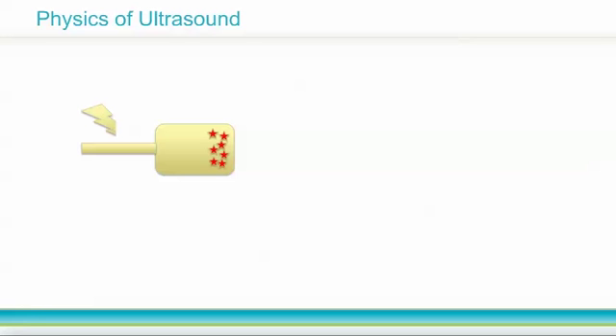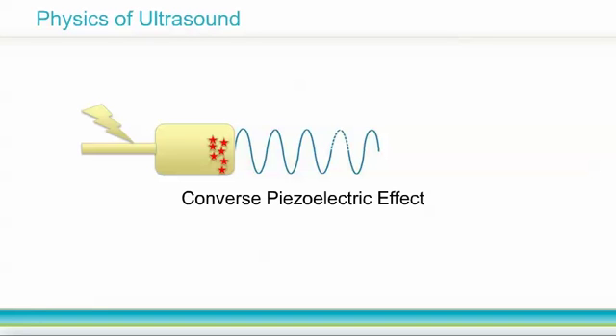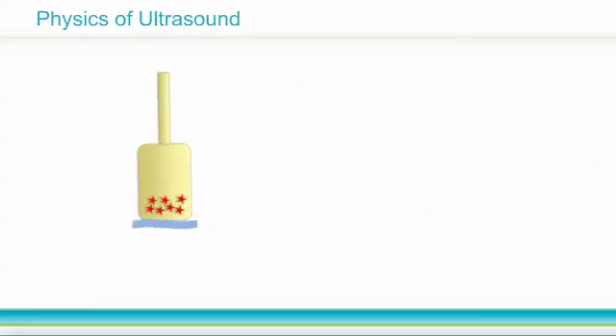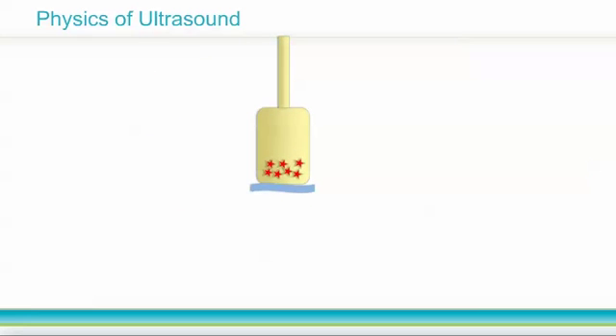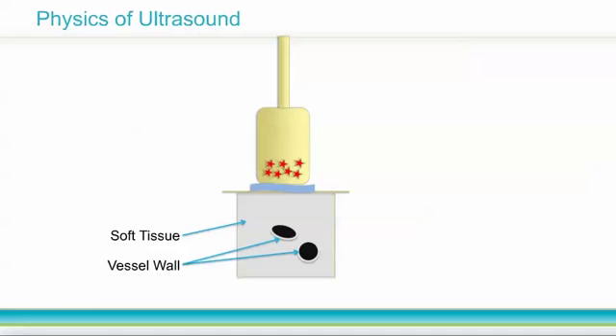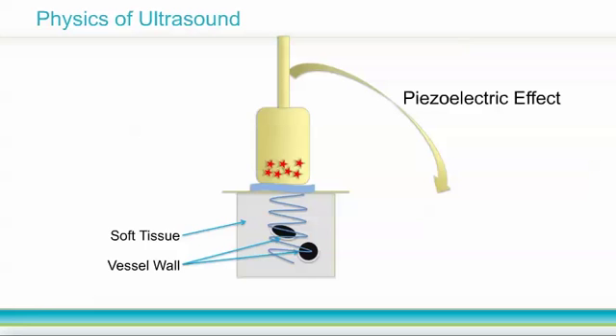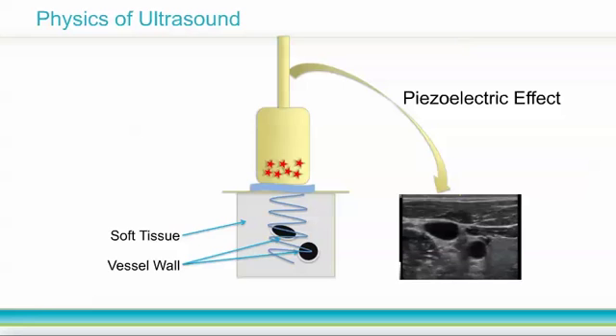Let's go through the steps that occur when we turn the ultrasound machine on and place the probe on a patient. Electricity is applied across the crystals in the transducer, causing them to vibrate and emit an ultrasound wave. This is called the converse piezoelectric effect. A layer of conductive gel helps facilitate penetration of the wave through the skin and into deep structures. The wave is reflected at the interface between tissues that have different acoustic impedances — for example, subcutaneous soft tissue and a vessel wall. The transducer detects the returning sound wave and transforms it into an electric signal. This is called the piezoelectric effect. This signal is then processed and displayed as an image on the screen.